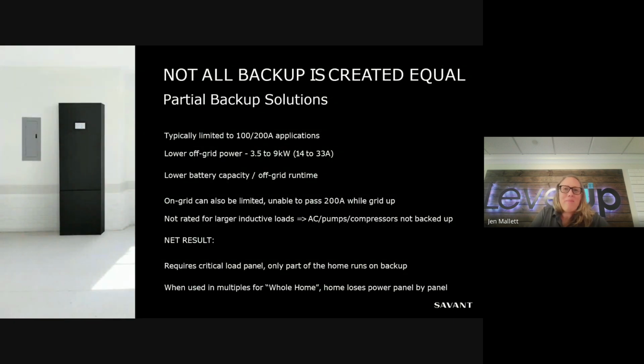Not all partial backup solutions are created equal. They're typically limited to 100-200 amp applications, with lower off-grid power—maybe only 3.5 to 9 kilowatts available, which is 14 to 33 amps. So it's not that powerful of a source. There's also lower battery capacity, meaning when the grid goes down, you might only get 2 or 3 hours of runtime for your devices—not much more beneficial than having another energy source available, like a generator.